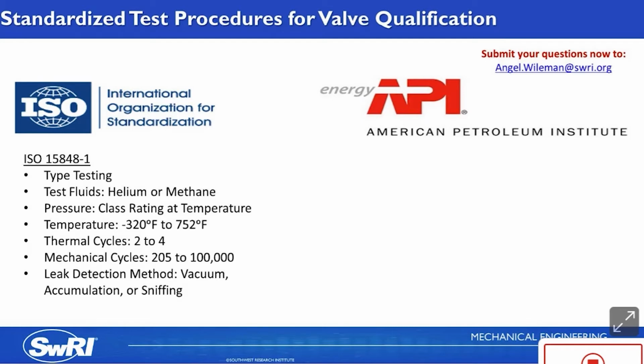Type testing is where you test a particular valve design, and once it's qualified, that qualification can be extended to untested valve sizes and classes of the same design if you meet certain conditions, which will be defined in the standards. The test fluid for ISO 15848-1 is helium or methane. The pressure is the pressure rating of the valve at temperature. The temperatures can range from -320 degrees up to 752 degrees Fahrenheit, and this depends on the qualification range of the valve.